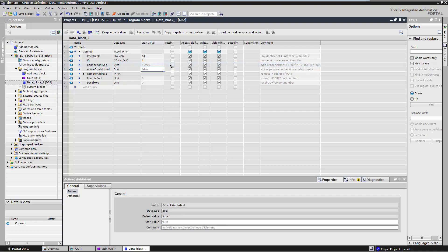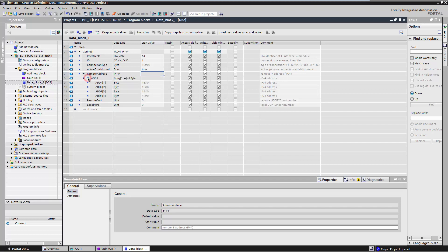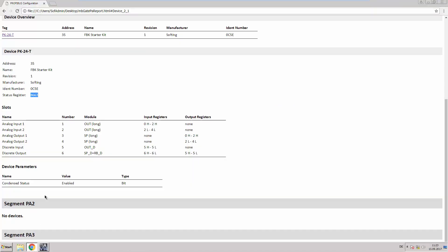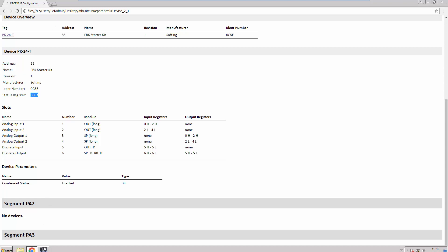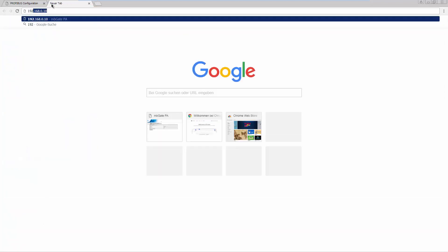Active_Established defines the type of connection. Enter true for establishing an active connection. In Remote Address, the IP address of the Modbus server must be entered. The IP address of the Modbus server in the MB-Gate PA can be found on its web server.